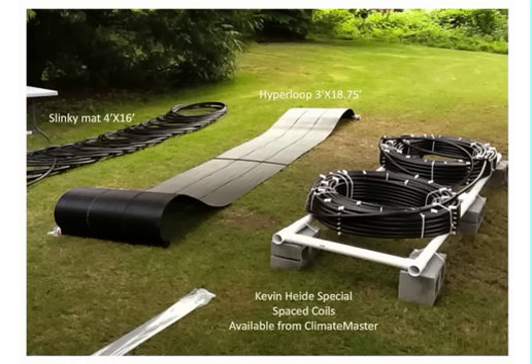You can see here the Kevin Heide Special, named after a gentleman down in the greater Oregon area. Slinky coils available again from Climate Master. This is a little 2-ton unit, each a 300-foot coil. We've manifolded these, and you can see the plastic PVC 2-inch pipe frame we use to create our spacing on the coils. I like to see 3 to 4 feet minimum between the coils.